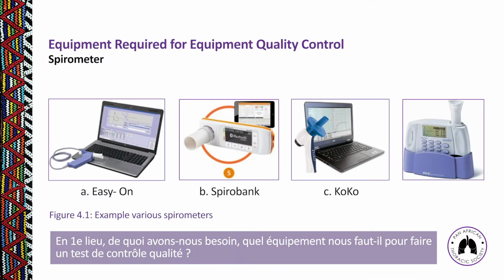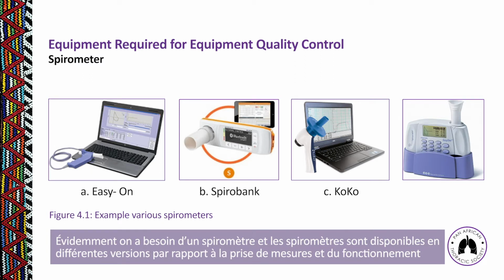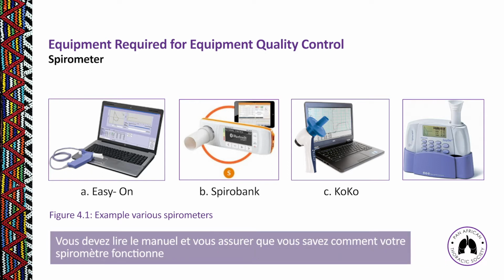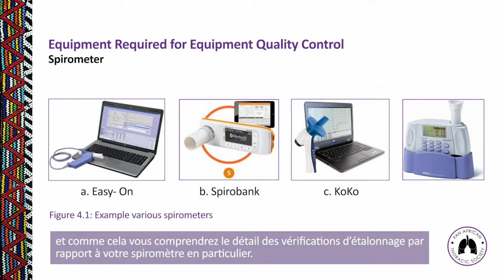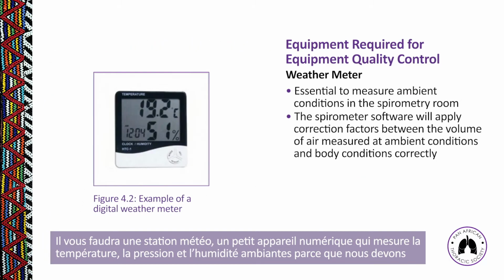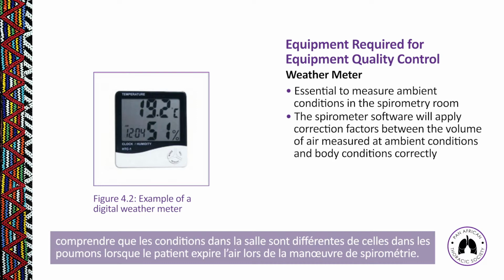So first of all, what do we need? What equipment do we need to conduct a quality control check? Obviously, you need your spirometer, and the spirometers come in various measuring and operating principles. It's important that you read your manual and you understand how your spirometer actually works so that you can understand the ins and outs of calibration checks specific to your spirometer itself. You will need a weather meter, a little digital device that measures ambient temperature, pressure, and humidity, because we need to understand that the conditions in the room are different to the conditions in the chest when the air is expelled from the patient in a spirometry test itself.